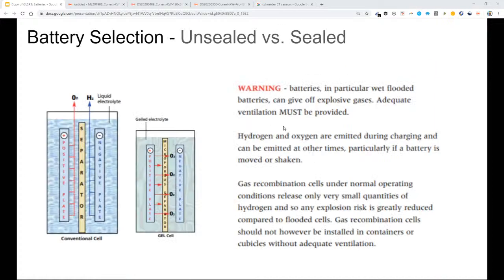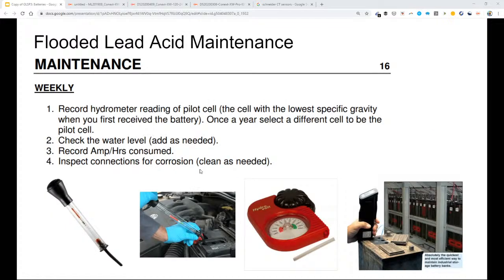This is stuff we'll talk about more in the off-grid battery class. But even basic things like, let's say the cheapest lead acid battery was in fact the cheapest and therefore a viable option to consider - a sealed battery, because it doesn't produce gas, can be in an unvented cabinet. A battery that gets large enough for commercial systems, or a battery that emits gas on its own, has to have ventilation requirements built into fire code, including continuous ventilation.